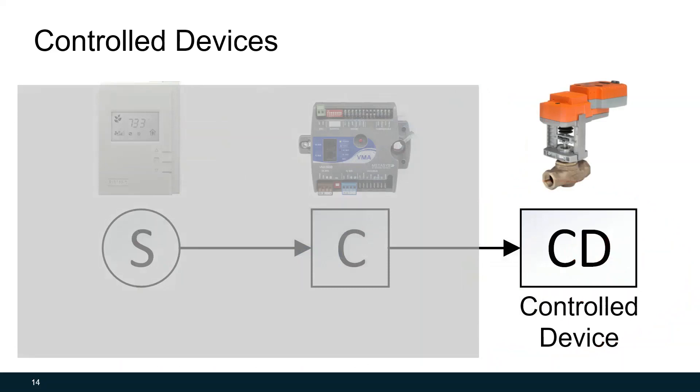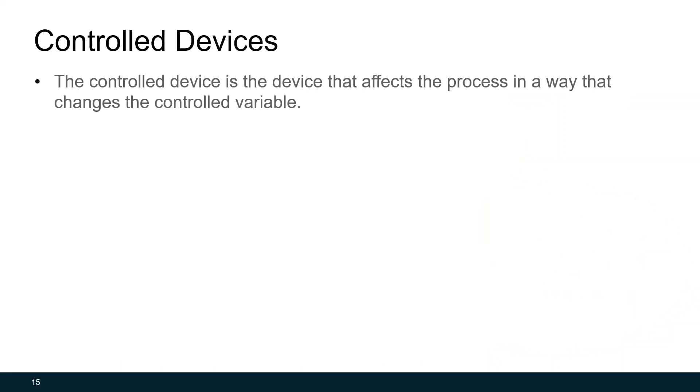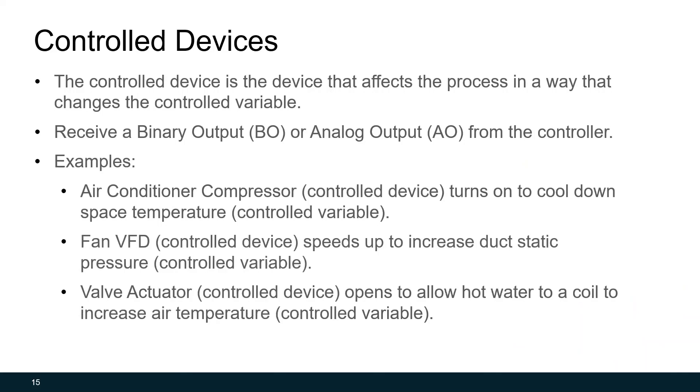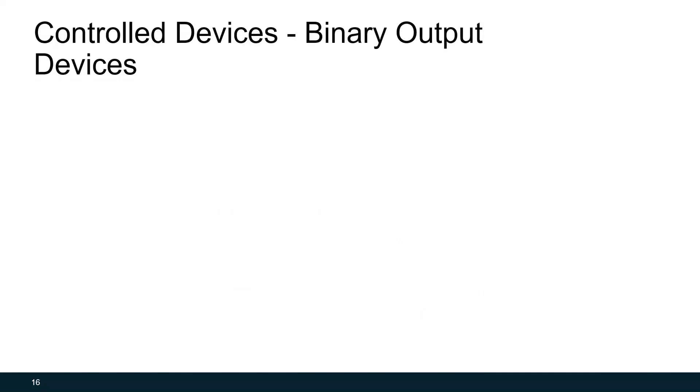The last part of the control system is the control device. The control device is simply the device that affects the process in a way that changes our controlled variable. And these receive binary outputs or analog outputs. Some examples of control devices affecting the controlled variable would be your home air conditioning unit, which has a compressor. We can turn that on to cool down space temperature. Perhaps we have a fan with a variable frequency drive or VFD, and we want to speed up that fan to increase duct static pressure to increase the flow rate through our system. Or, as in our previous example, we have a valve that needs to open to allow hot water to a hot water coil to increase air temperature.